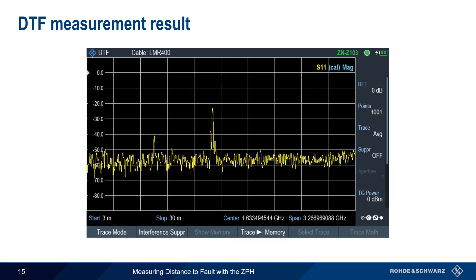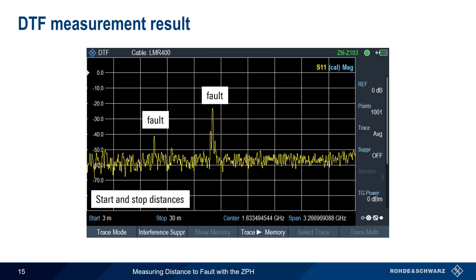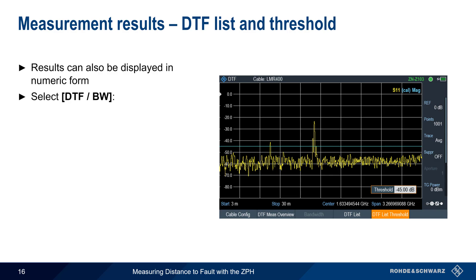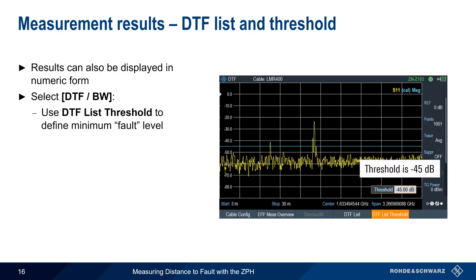After disconnecting the calibration standards or unit and attaching the cable under test, the distance to fault measurement will run automatically. Here we see a typical measurement result, showing two potential faults in the cable. The start and stop distances are shown along the bottom of the screen, as are the center frequency and span.